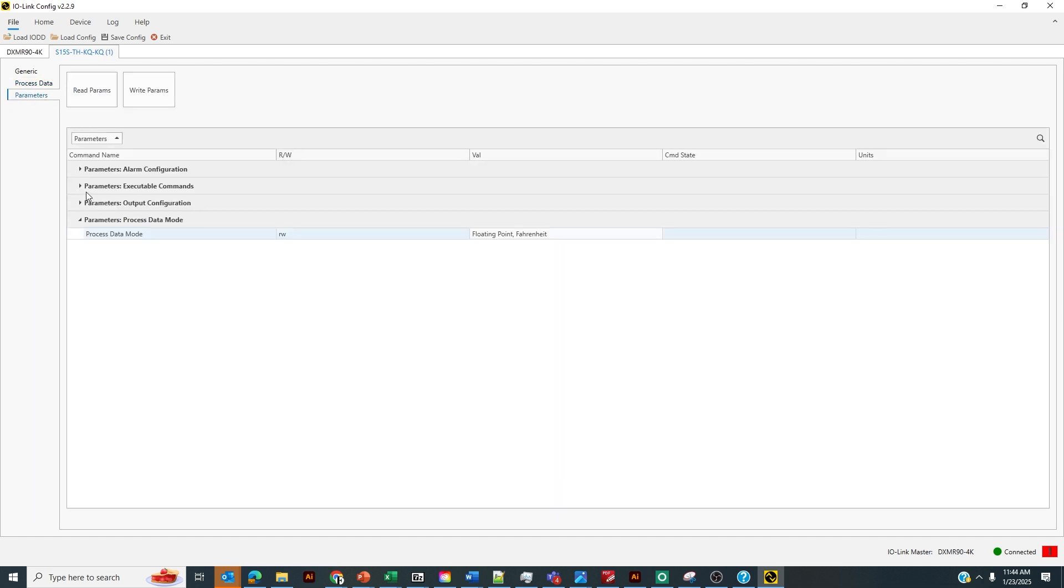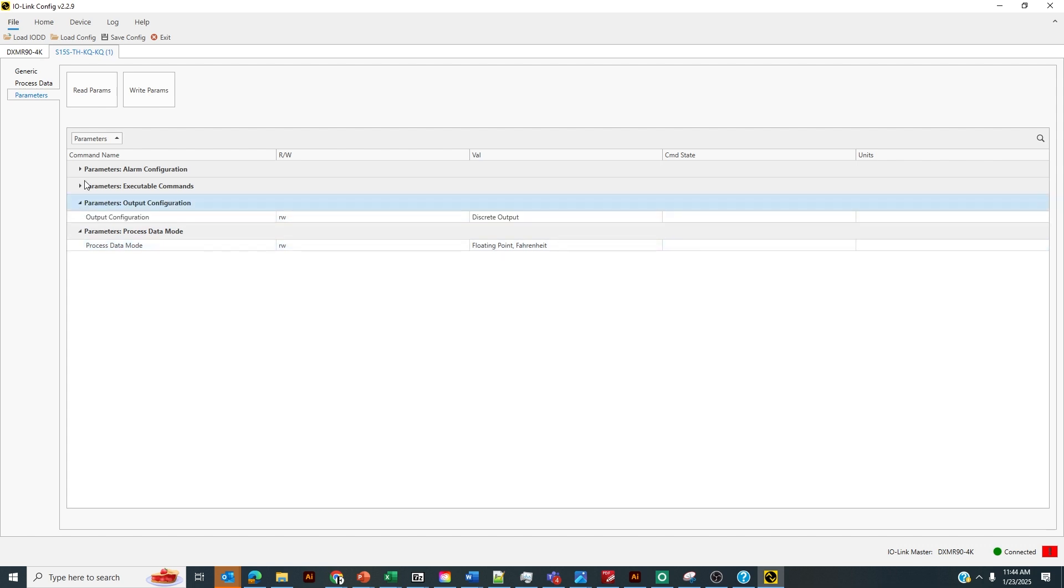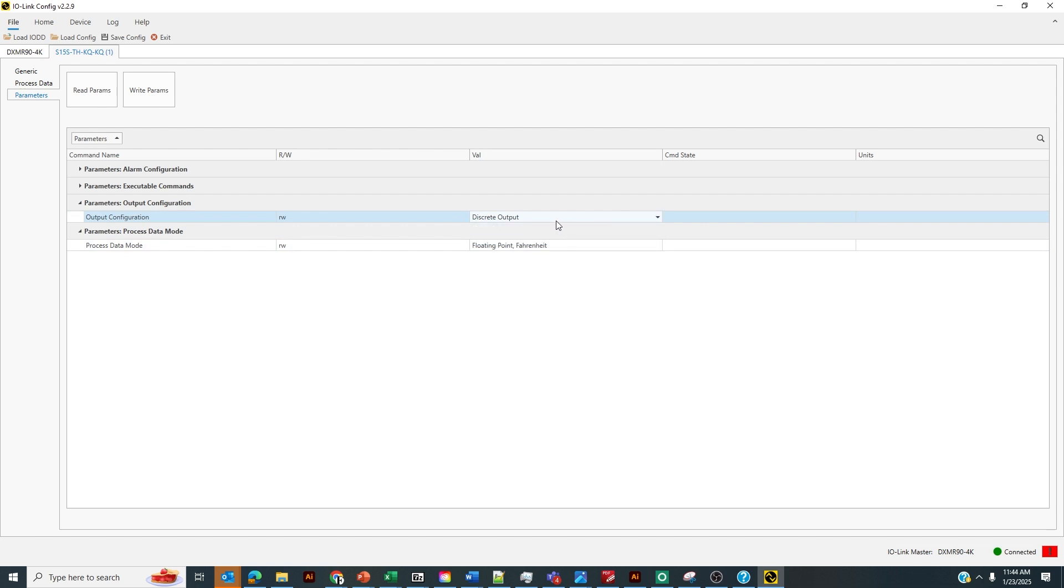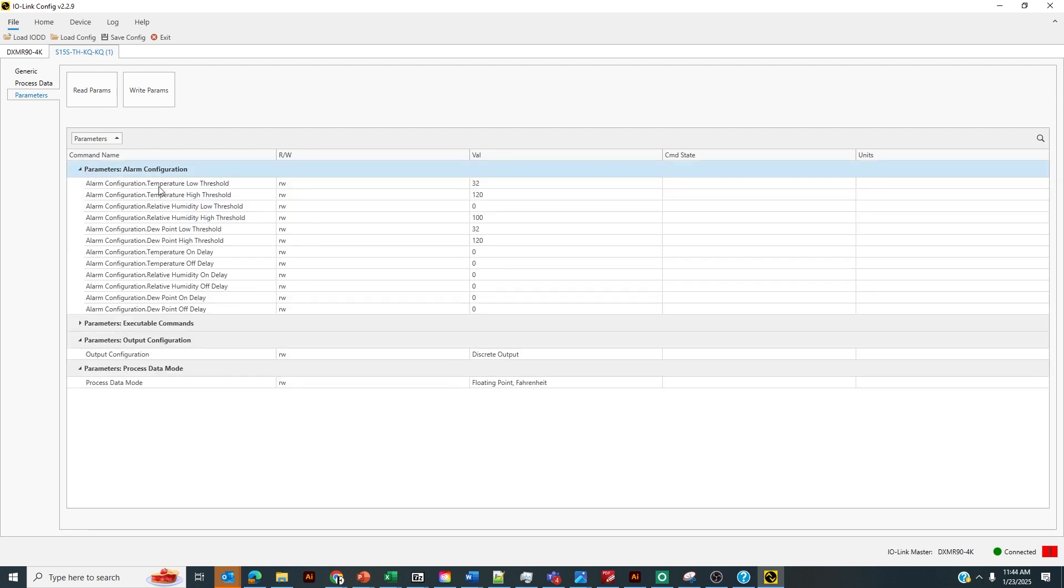Another thing that's unique about this sensor is that we could program it to have a discrete output on the white wire, pin 2, when a certain threshold is exceeded on the temperature value, the humidity value, or the dew point value. If we go to Alarm Configuration, we could set those thresholds for that discrete output to turn on on the sensor to turn on or actuate that light that we have connected.